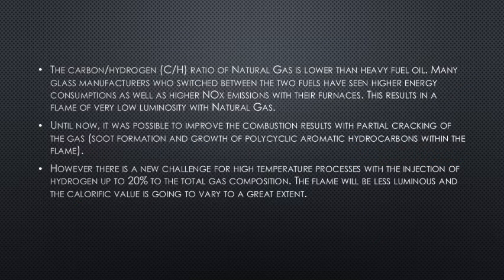So for different fuels, for example natural gas and heavy fuel oil, the carbon hydrogen ratio is lesser for natural gas. Many glass manufacturers who switched between these two fuels have seen higher energy consumption and higher NOx emissions in the case of natural gas.